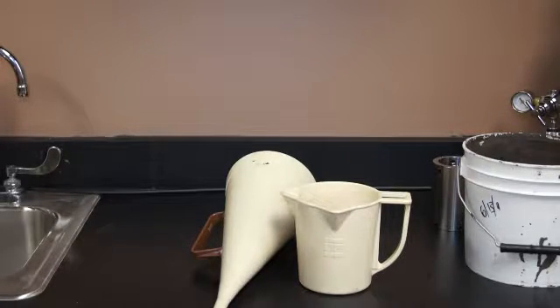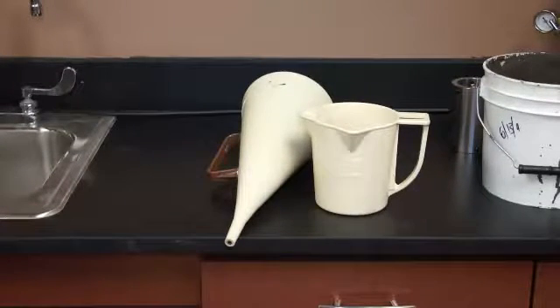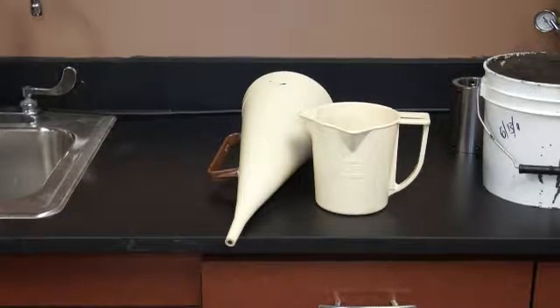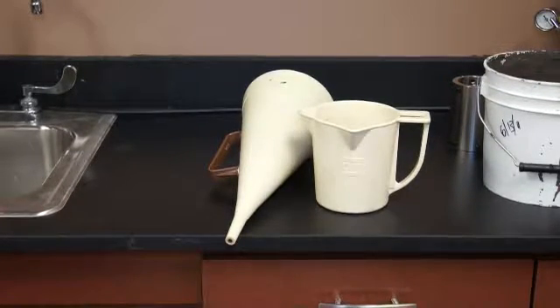So again, as I say, this is a relative viscosity, and it works very well for what it does. Basically, you're looking for trend analysis. If you get 43 seconds, 47 seconds, 38 seconds, and all of a sudden you get 85 seconds, then you know something has changed in your fluid. You don't necessarily know what has changed or why that change was made, but you do know that something has changed in the fluid, so it's time to do something.